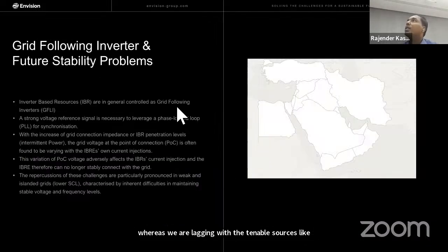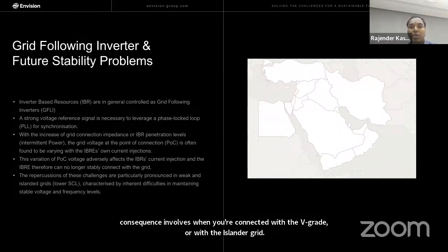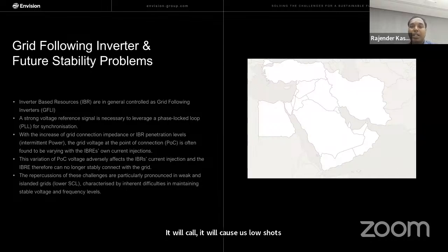Going to the next point, in the MENA region, what is another problem when we are integrating grid following inverters? With an increase in the grid connection impedance, the voltage at the point of connection is often found varying with the renewable current injection, because larger plants are connected to the grid. The dynamic interaction will give a stability challenge when coupled with more inverter-based resources. The consequence is that when you are connected to a weak grid or an islanded grid, it causes low short circuit levels, and these grids inherently struggle with maintaining stable voltage and frequency levels. So it is a significant, technically complex challenge to solve.